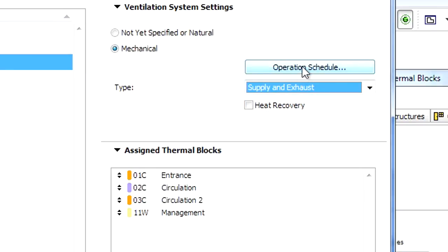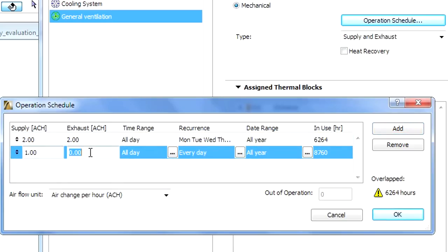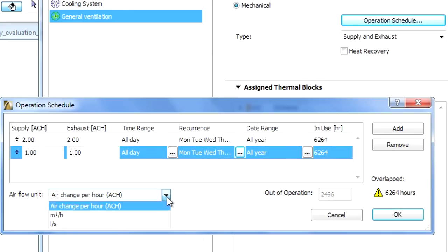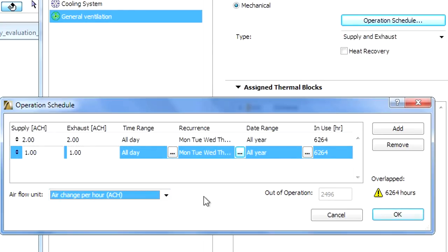The air exchange rate can be set with different time ranges in the Operation Schedule. Here we can reduce the energy loss due to Ventilation by scheduling the Ventilation Intensity on a daily and weekly basis. The Ventilation Intensity can be reduced for the non-working time periods. We can change the unit of the air flow amount with the help of the pop-up list. Mechanical Ventilation systems may or may not have air-to-air heat recovery units, specified by a dedicated checkbox. An air-to-air energy recovery system can regain a percentage of the heat content of mechanically expelled ventilation air.